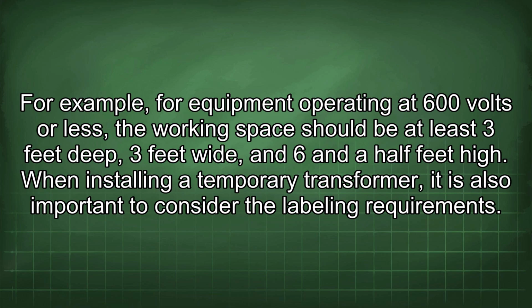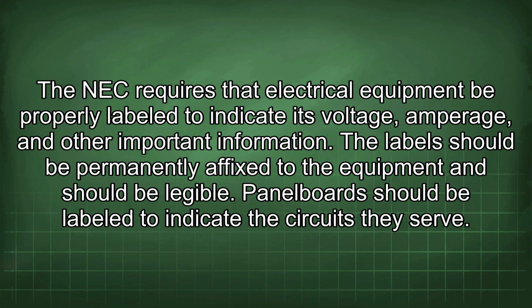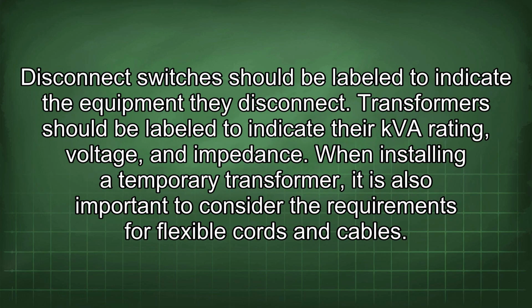When installing a temporary transformer, it is also important to consider the labeling requirements. The NEC requires that electrical equipment be properly labeled to indicate its voltage, amperage, and other important information. The label should be permanently fixed to the equipment and should be legible. Panel boards should be labeled to indicate the circuits they serve. Disconnect switches should be labeled to indicate the equipment they disconnect. Transformers should be labeled to indicate their kVA rating, voltage, and impedance.